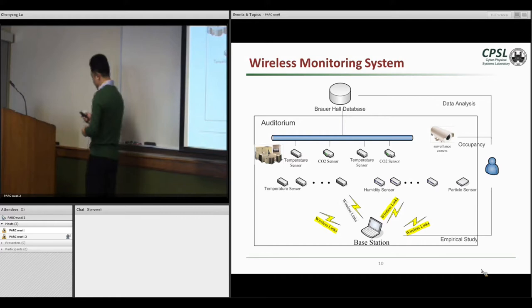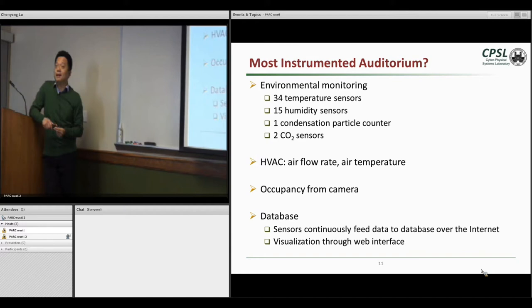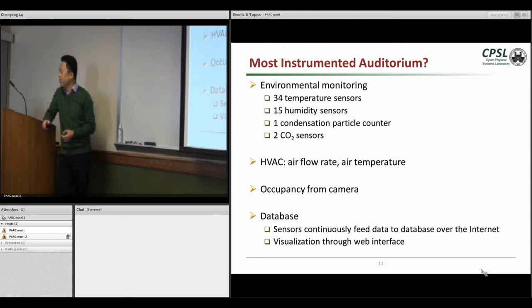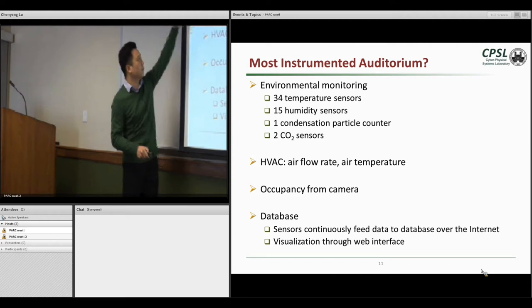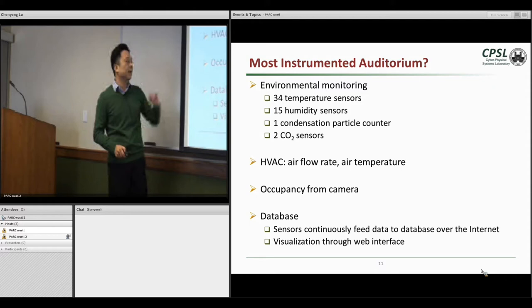So in the end, we suspect what we made is the most instrumented auditorium in the world, potentially. It had 34 temperature sensors, 15 humidity sensors, one condensation particle counter, which is a proxy for air quality, and two CO2 sensors. We also try to correlate these phenomena with HVAC operations in terms of airflow rate and air temperature data, and correlate that with occupancy from the camera.